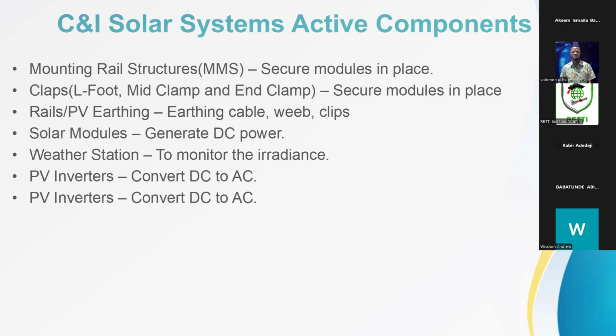Okay, so I talked about the PV inverter. Now we have the PV inverter combiner panel. In a system where you have PV inverters, like the example we gave, let's maintain the example of a 300 kilowatt system. We said we will need 5 PV inverters. If you have 5 PV inverters, you don't run each of these PV inverters to the controller separately. So instead of that, what we do is use what we call a PV combiner panel.